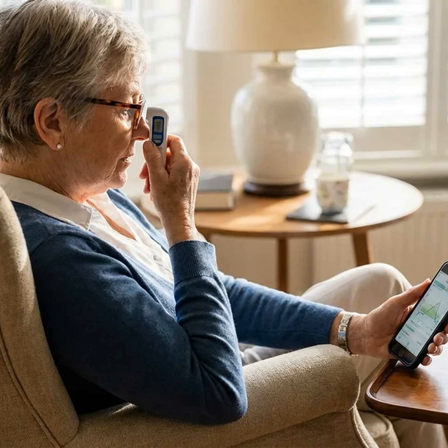Thin or thick corneas can also skew results because rebound devices, like any tonometer, are influenced by corneal properties. In fact, manufacturers recommend iCare Home only for corneal thickness between about 500 to 600 micrometers. Outside this range, the readings may be less reliable. Complex eye conditions, like after certain surgeries, might also affect probe alignment and results.